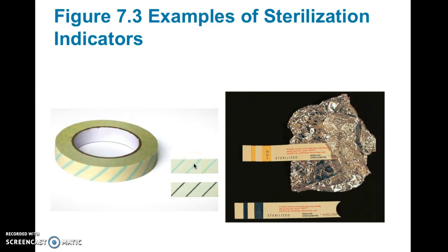If it hasn't, if you come back and your tape is still yellow or pale blue, you know that something is wrong with the autoclave. You need to adjust the settings or check it or clean it or use a different autoclave because whatever you put in was not sterilized. There's also little paper strips that change color. There's many different variations on this type of thing, but the important thing is you have to have something in there that tells you whether it got to the high enough temperature and pressure that actually sterilized your equipment.